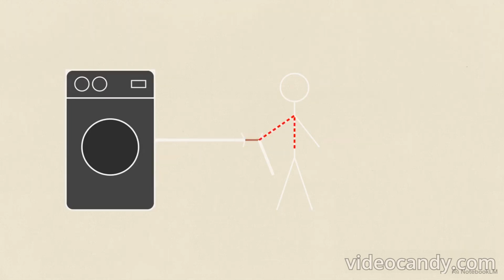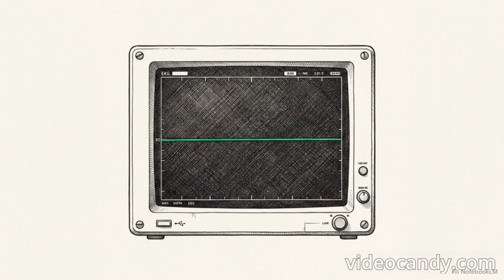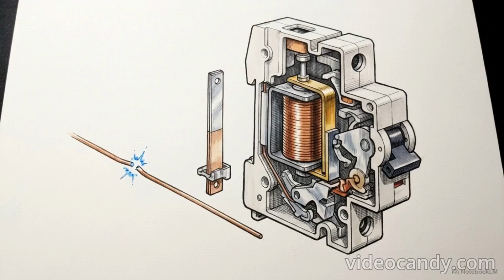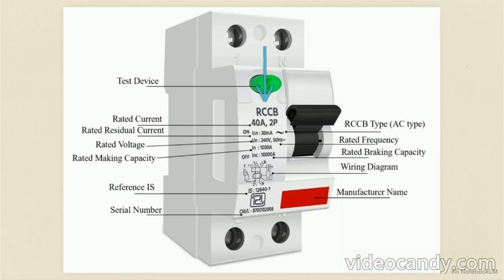If a person touches an exposed wire, a line-to-ground fault occurs through their body. The current required to stop a human heart is a fraction of an amp. A standard 20 amp MCB will never detect this. The current volume is too low to bend the bimetallic strip or trigger the magnetic solenoid. To protect biology instead of copper, we rely on the residual current circuit breaker, or RCCB.